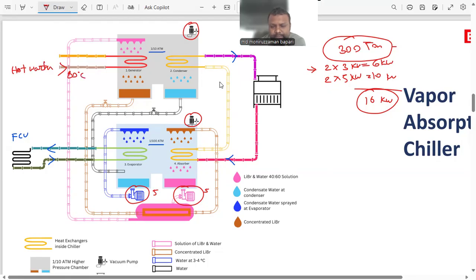Let's say at 80 degrees centigrade. So if you can generate hot water by a cheaper means, you can run the whole show very, very efficiently. For instance, if you have the availability of any waste heat, the waste heat can be used to boil up the water at 80 degrees centigrade, and you can use it to run the chiller, which will be very efficient. And sometimes, depending on the country, the oil is very cheap if you are living in the Middle East, and sometimes in places where natural gas is very cheap, then you can run it on gas.